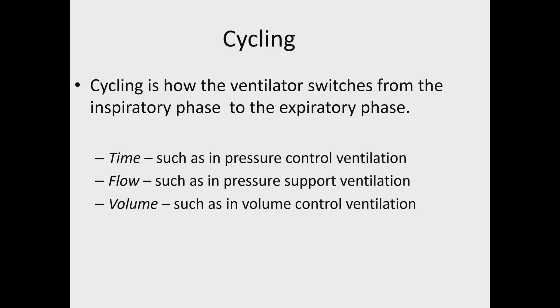Similarly with flow, if the ventilator senses that inspiratory flow has decreased to a certain point, it will cycle the ventilator to exhalation. With volume ventilation, such as assist-control, once the set volume has been reached, the mechanical ventilator will then cycle the breath to the expiratory phase.